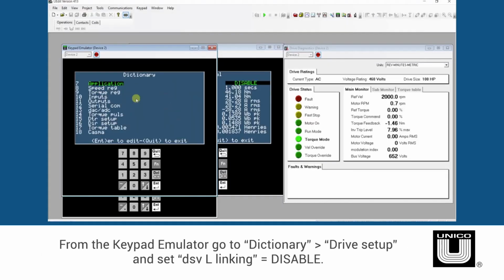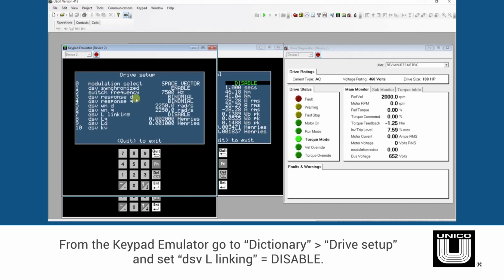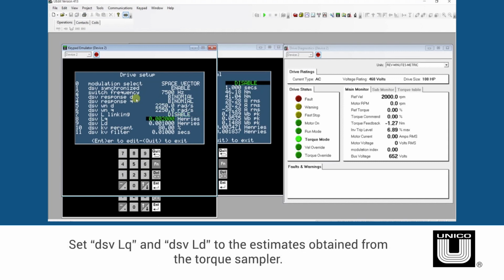The next step is to use the LQ and LD estimates for the current regulator tuning. From the keypad emulator, go to Dictionary, Drive Setup, and set DSV L linking equal to disable if not already done. Then set DSV LQ and DSV LD to the estimates obtained from the torque sampler. In this example, I have values slightly below the estimates to prevent overtuning the current regulator, which could result in current oscillations.